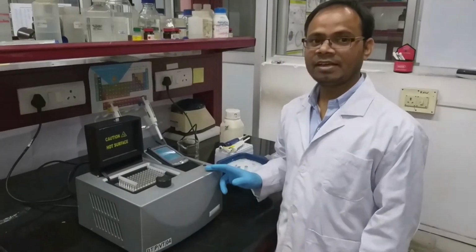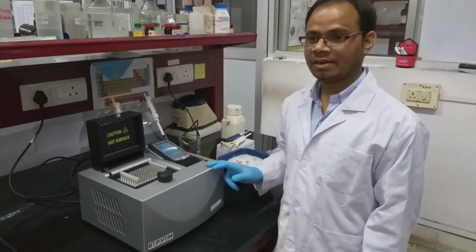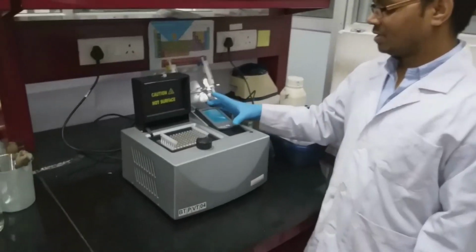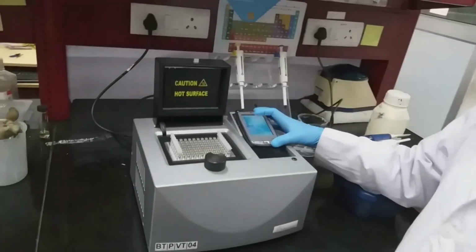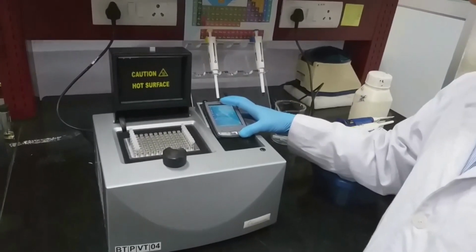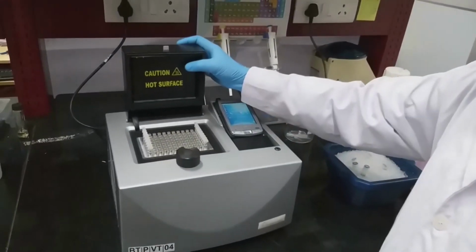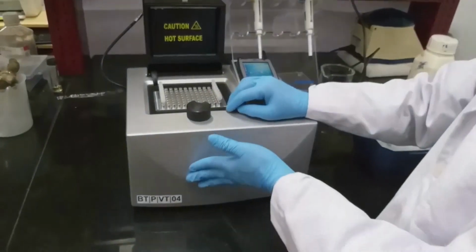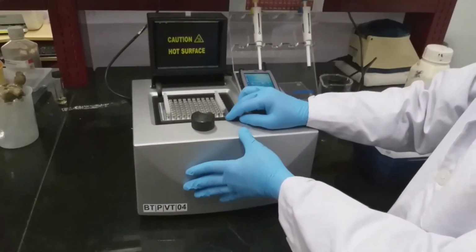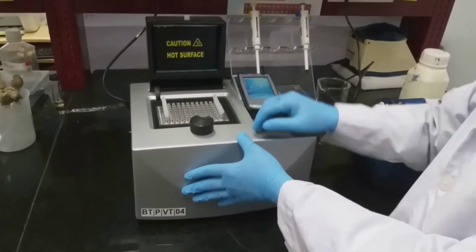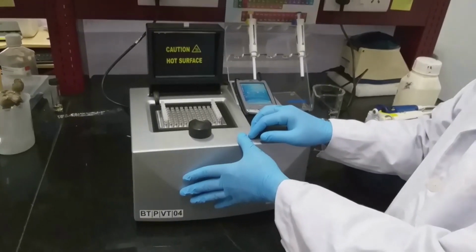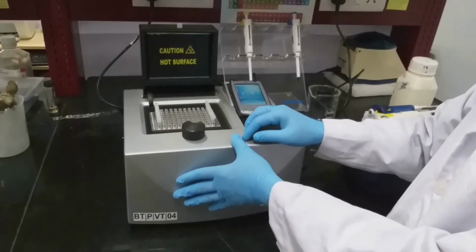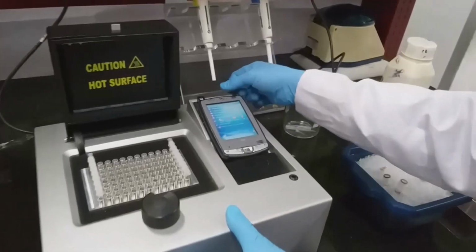This is an earlier version of a thermal cycler which contains a display unit where we can observe the parameters and change them. This is a hot shield, this is the sample holder, and inside there is a Peltier system which can maintain the temperature fluctuations.